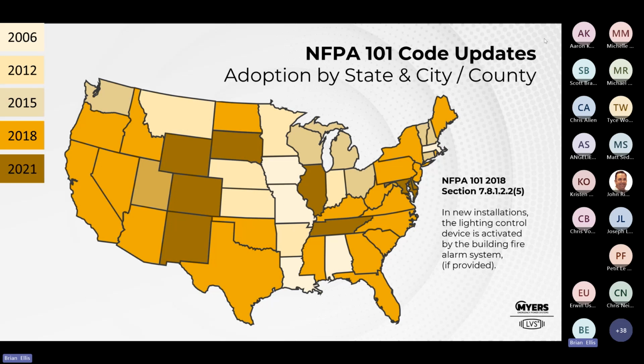So think about, right now our path of egress controls and our path of egress lighting, our inverter, generator, bypass relays, all of this system, what it's doing is it's only providing this path of egress lighting when utility fails. So what happens if we have a fire? There's smoke covering the lighting control occupancy sensors, but the fire hasn't taken out utility. So we could be in a circumstance where we're leaving the building in the dark, which would be problematic, to say the least. So this is a good idea to provide a fire alarm override for the path of egress, even though maybe it's not adopted by your state. So just something to think about.